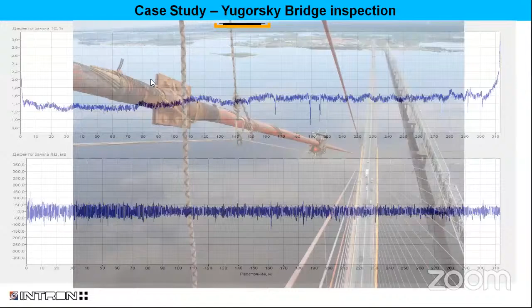And ultimately, the customer took emergency measures to prevent this kind of damage from spreading. We've re-inspected the bridge 10 years later. So the first image was from 2009. This is 2019. And even though obviously we couldn't stop this damage, for the rest of the cable there's no deterioration since then. So obviously the customer had a huge relief that he did not have to replace a cable, and you can imagine how much it cost them.